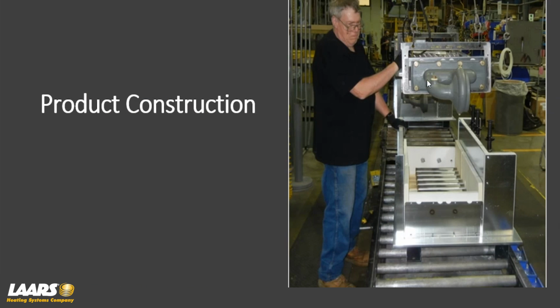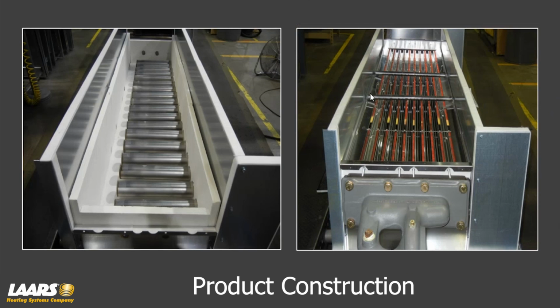On the product construction, they pressure test the heat exchanger, and here we're showing one with a pump volute on it. On the return header, they've added a pump volute, so it was being ordered as a pump-mounted boiler. So again, they pressure test. They use an overhead crane, so you can see some cables here to bring those over into position, and then they drop those and set those into position on top of the combustion chamber.